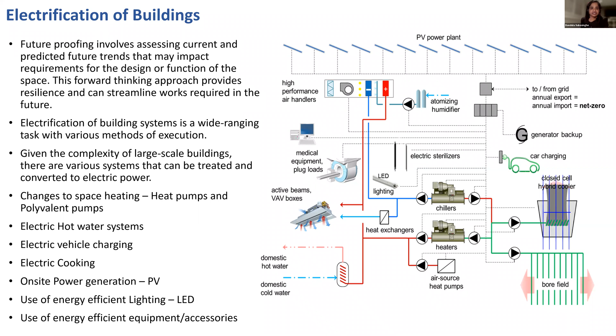This is an example from one of my projects where we implemented roof-mounted PV cells along with mechanical systems: air heat pumps and a combination of water-cooled chillers and cooling towers. The water-cooled chillers and cooling towers provide about 40% of the cooling, in a polyvalent system that can provide both cooling and heating, while the heat pumps purely provide heating.